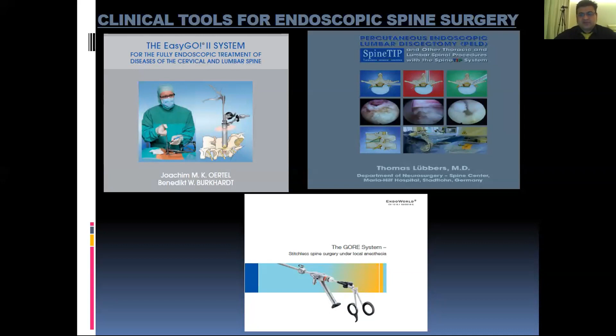In the rigid endoscope, you have a rigid rod lens system where the rigid rod lenses are engraved in the shaft, followed by a light transmission bundle engraved with a camera head, and you get an image on the video monitor. And the image is definitely far, far superior to the flexible. But I will introduce you to a new flexible technology.